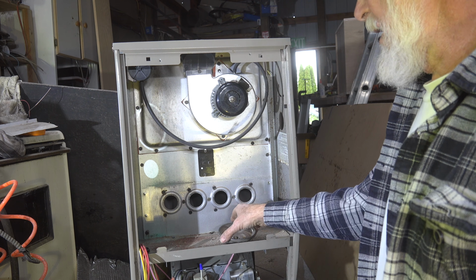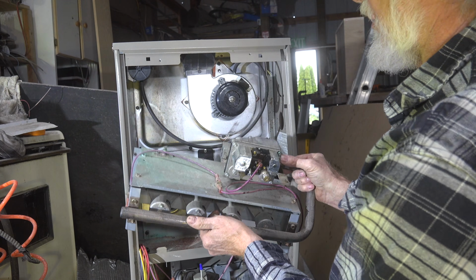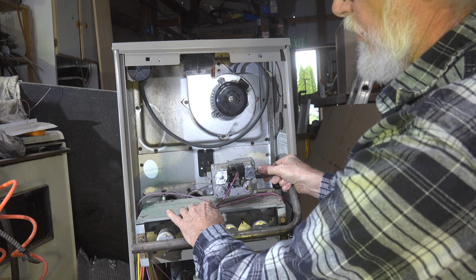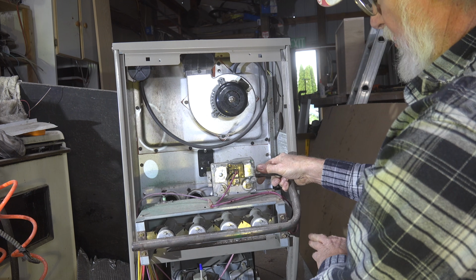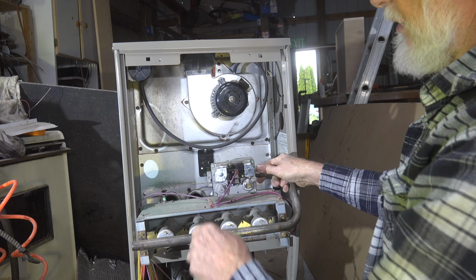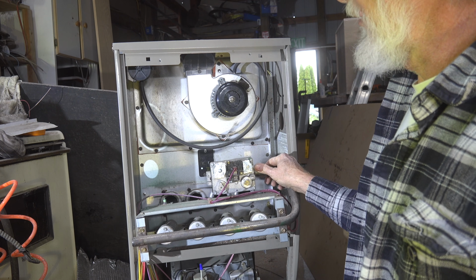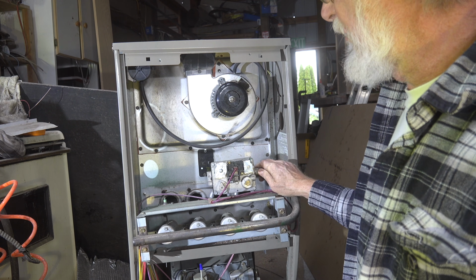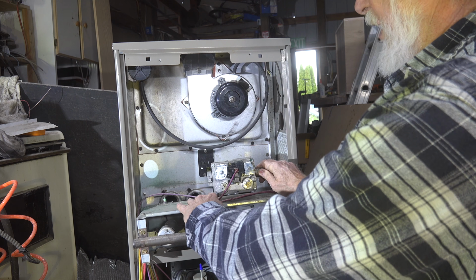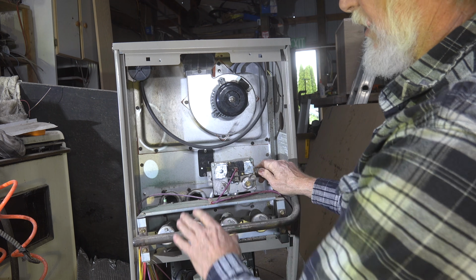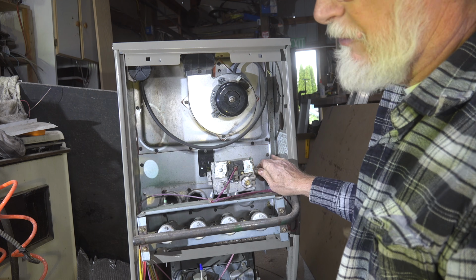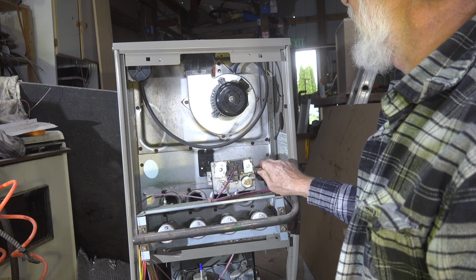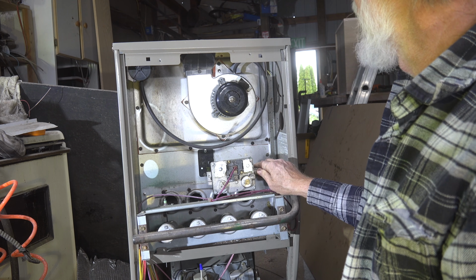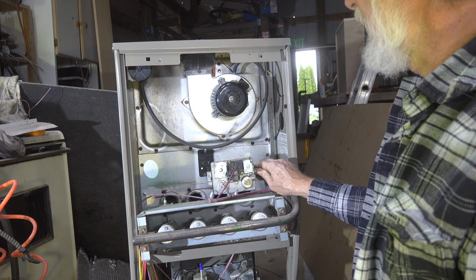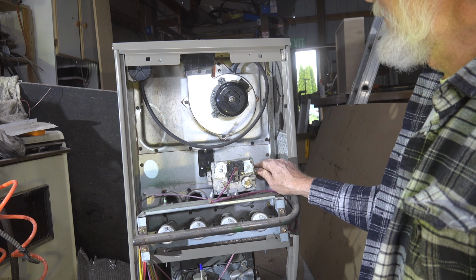Usually what happens is one of these rollout switches, probably the top one, but there's three here. If the rollout switch has been kicking off, I would replace it. Generally, this one's going to be the one that's going to kick off. But whichever one does, can't hurt to replace all three if you want. Anyway, this is ready for this assembly to go back in.